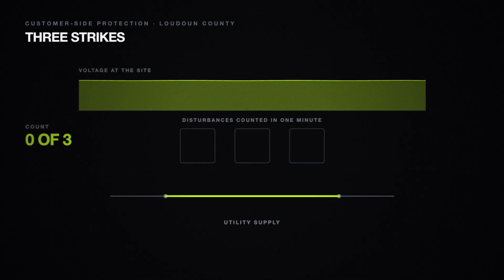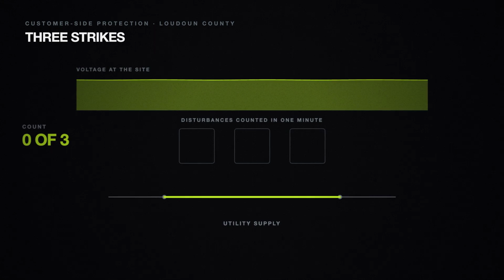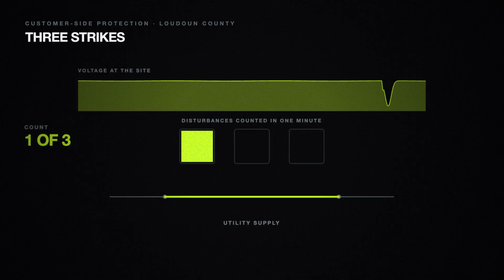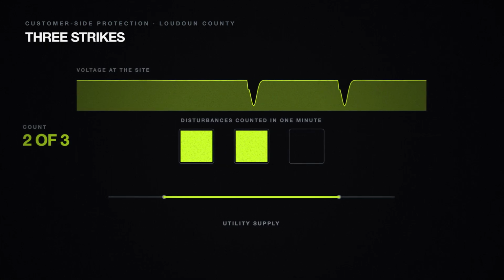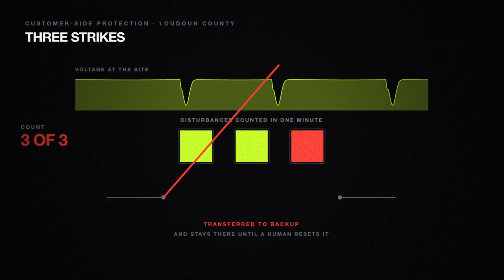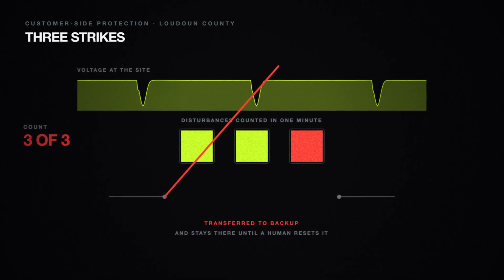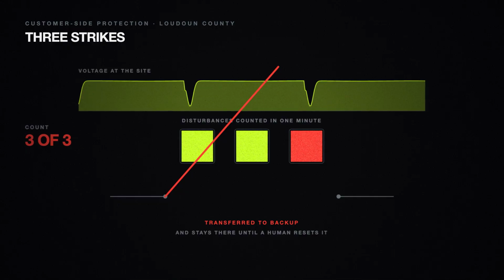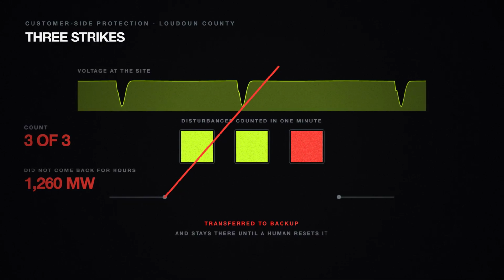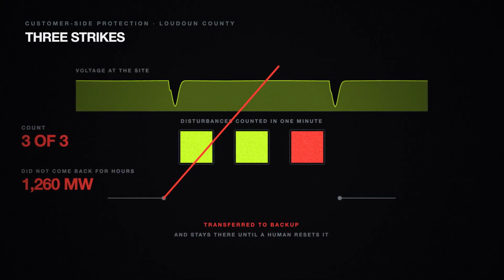That is a sensible rule for one building. The building's owner is protecting equipment worth more than the power. But the reclosing sequence on that line produced 6 voltage depressions in 82 seconds. 3 was the threshold. The 60 load points did not decide independently to leave. They all met the same criterion at nearly the same moment because they were all watching the same line. Roughly 1,260 megawatts dropped out at the 3rd depression and did not come back for hours.